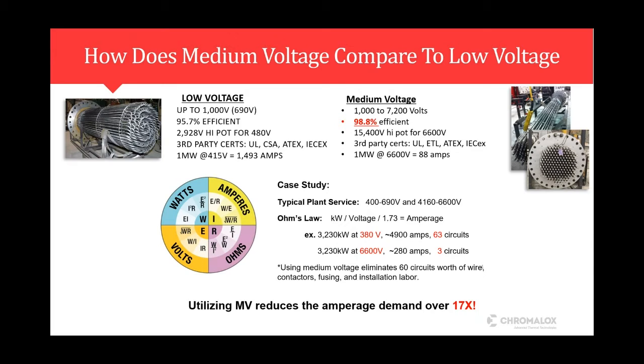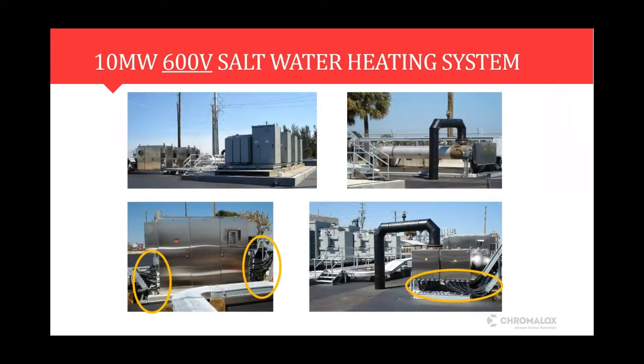So there's a lot of benefit you can realize, both from operational and maintenance and labor, by going up to those medium voltage systems. While I can sit there and talk about those details all day, the picture definitely helps paint a clearer picture for what that really means in the real world. So here's a 10 megawatt system at 600 volt, and you can just see all of the wiring and conduit that's needed to basically support that low voltage installation. Imagine that you have to terminate those wires and cables both at the heater side and the panel. So it's a lot of components through the fusing and the contactors and all the labor involved in that.